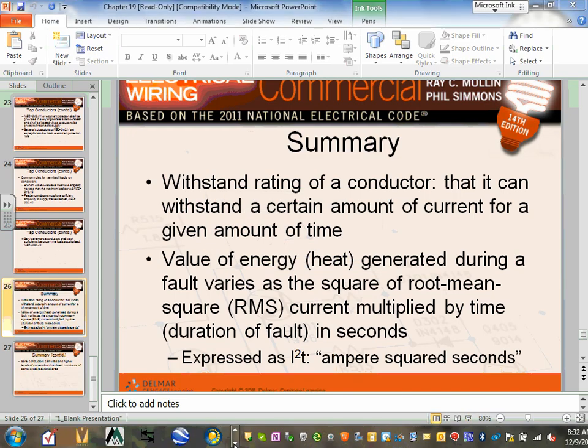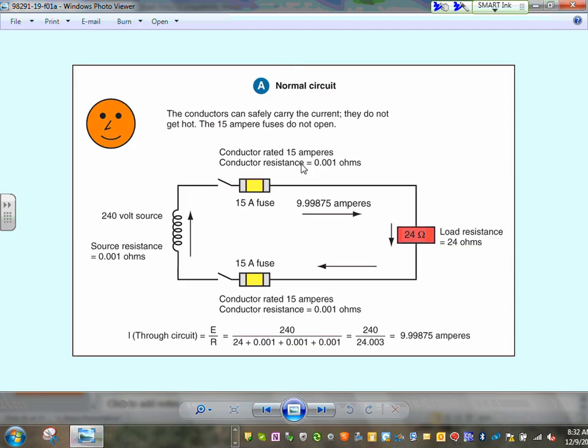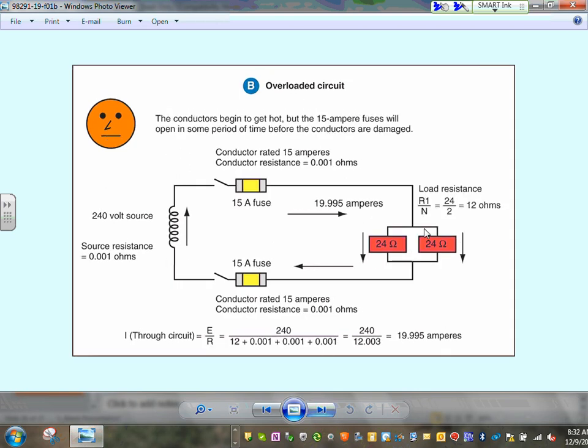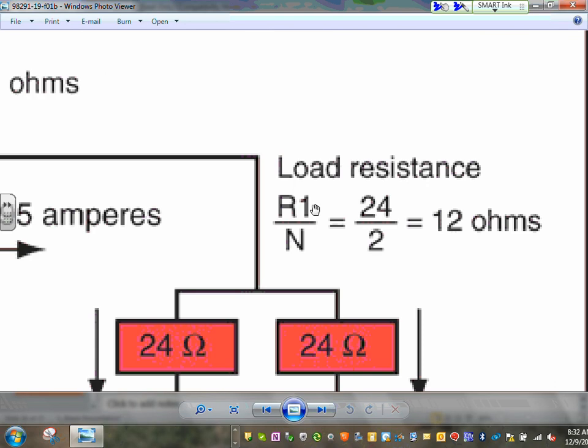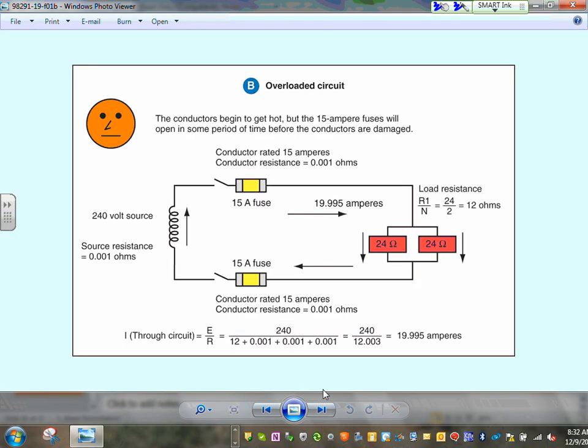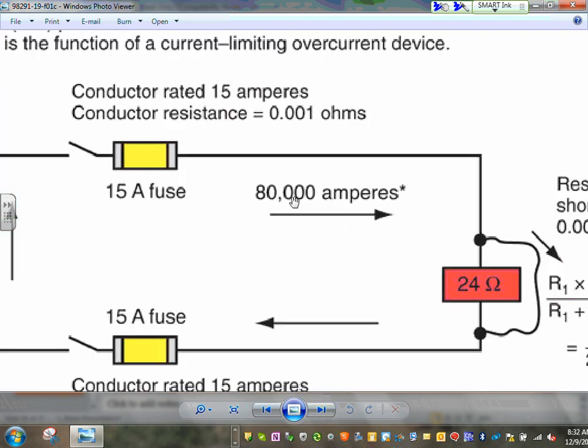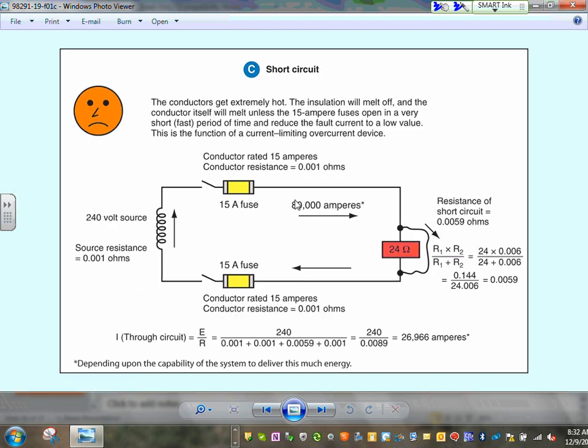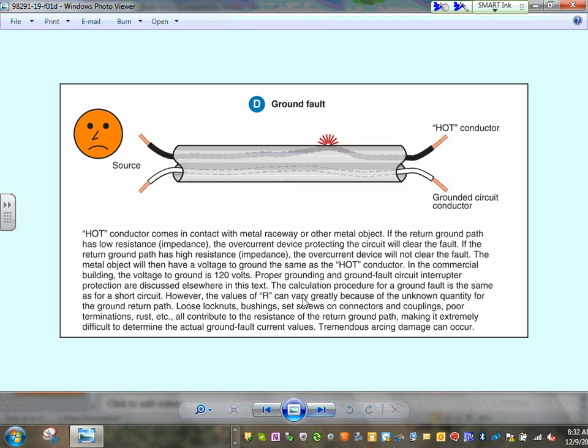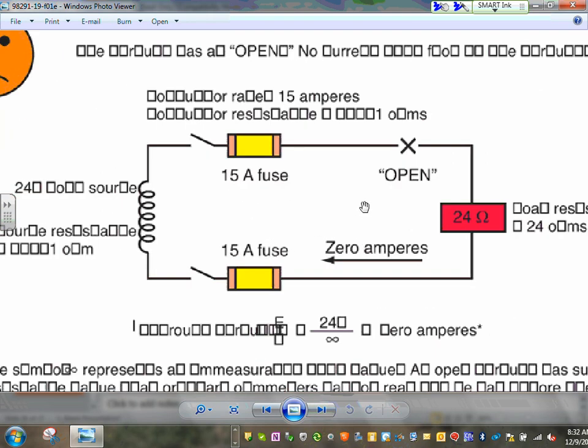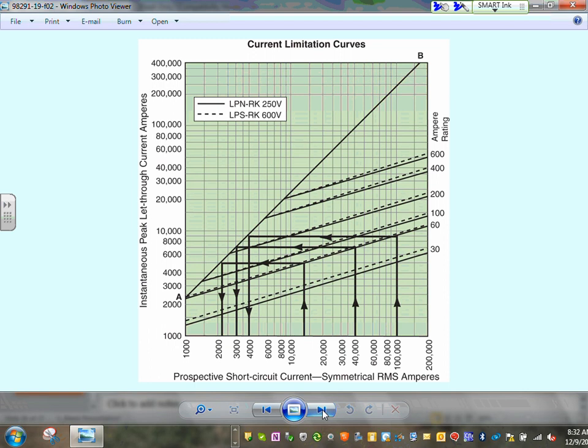Let me show you a couple of things here. We talked about the normal operation of the circuit. Derek, my friend, we said normal operation, everything is cool. Overload operation, can you see the current has doubled? The current has doubled here, the fuse will open. Short circuit, look at that. You got 80,000 amps, within seconds the circuit breaker will open. Ground fault, here's what a ground fault is, guys. You take the hot, touch the conduit, you got yourself a ground fault. That will typically be half of the 3-phase short circuit. Open condition, we talked about the open condition situation.